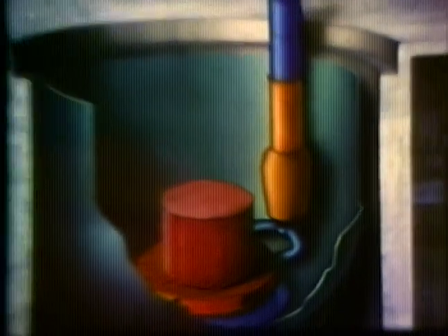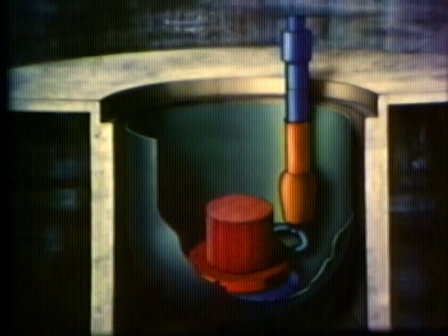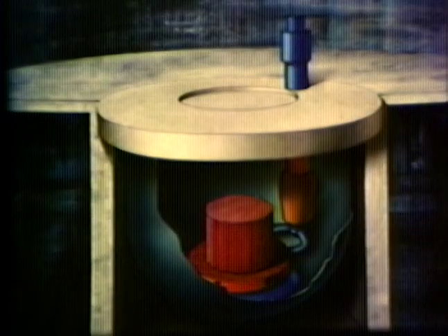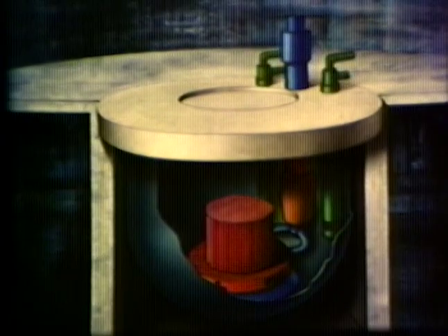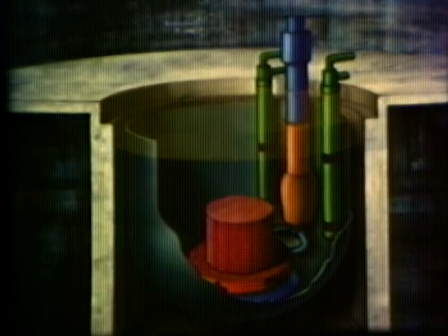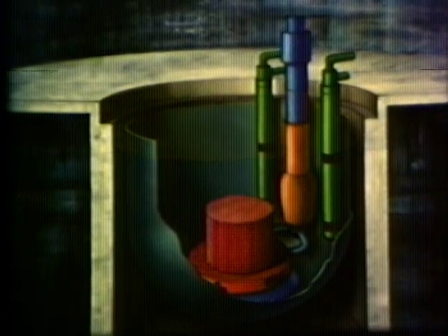The bottom section of the pump body is 2.5 meters in diameter and over 22 meters high. Combined with its electric drive motor, it extends 8 meters over the upper slab, which supports the entire weight of the pump, 150 tons. 2 intermediate heat exchangers are associated with each primary pump to provide symmetrical flow of the primary sodium.